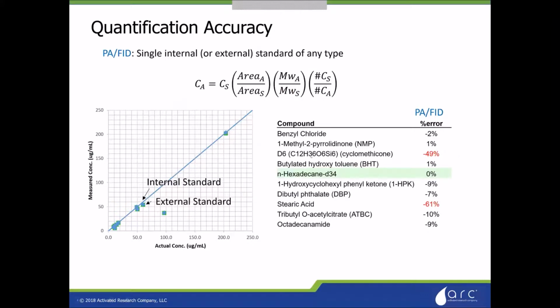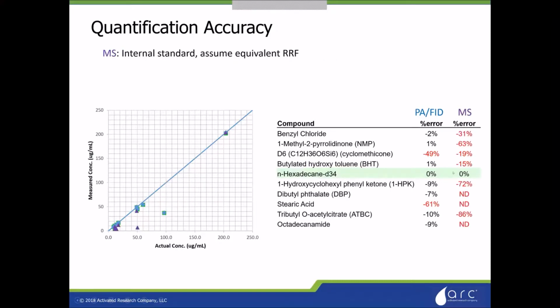If you look at then the quantification using the polyarc, you can do a single injection and use an internal standard and get very good accuracy, within 10% for all the molecules except for two. The cyclomethicone and the stearic acid, those two probably degraded in the inlet sample beforehand, something we're working with Abbott to learn more about. But what you can do here is in a single injection get very good accuracy for a number of different peaks. If we compare that to a mass spec, we are on the order of between 15% and 90% error with three molecules that weren't detectable at all because of their size and concentration there.